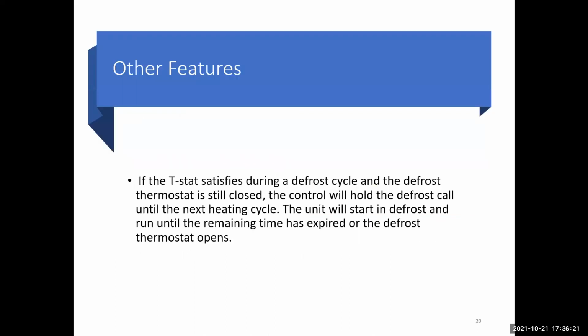Other features: if the thermostat is satisfied during the defrost and the defrost thermostat is closed, the control will hold the defrost call until the next heating cycle. The unit will start in defrost and run until the remaining time has expired, or the defrost thermostat opens.